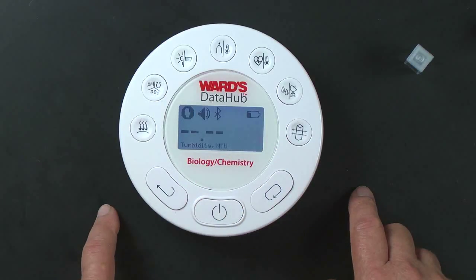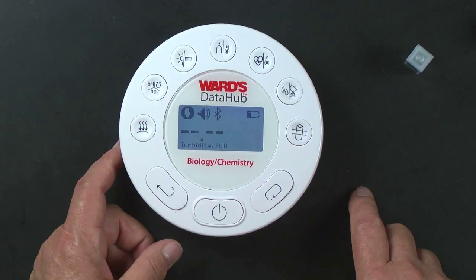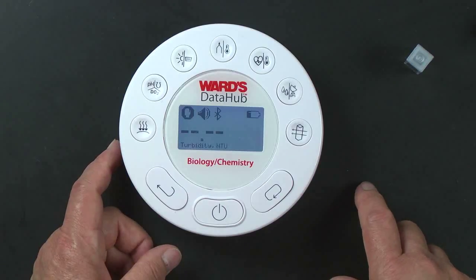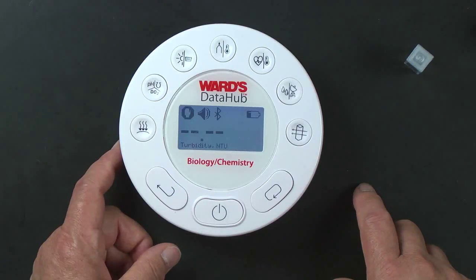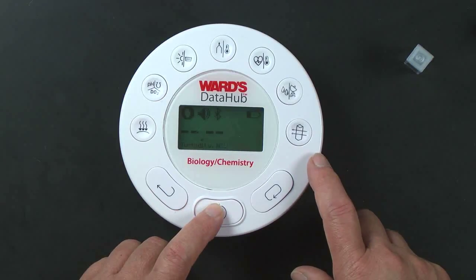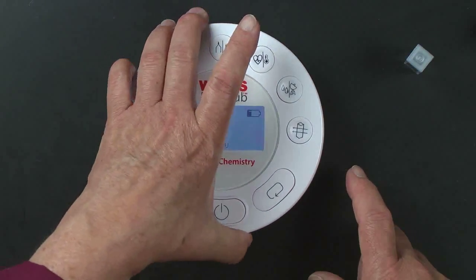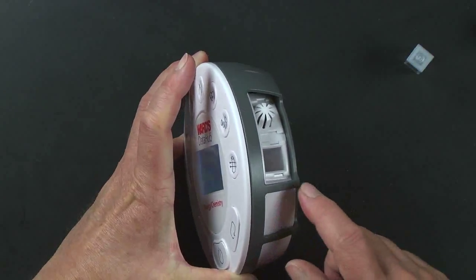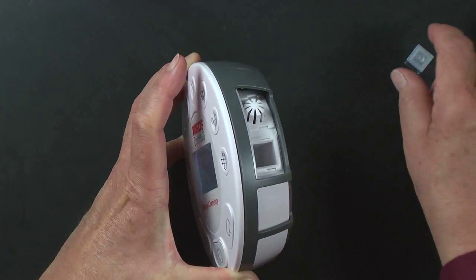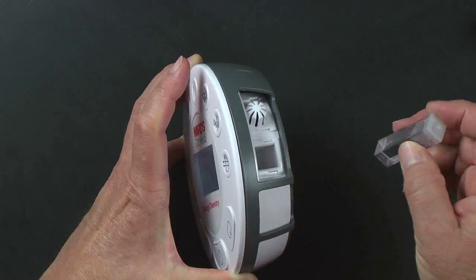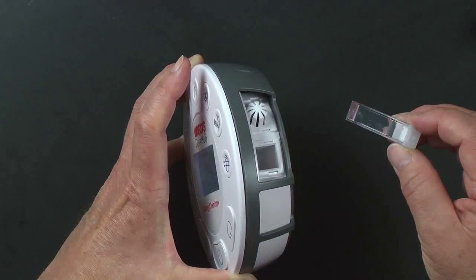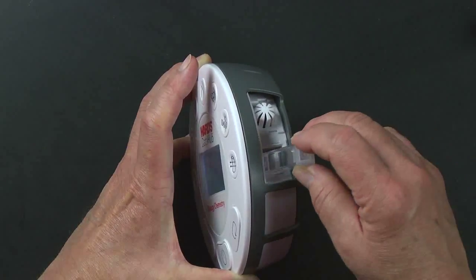and it also tests 3 different wavelengths of color. So it doesn't say, you can't set it as you normally see to 680 or 740 or something on a spectrophotometer, but it will give you a difference in readings. What you can do with these is you turn the Datahub again so that now you can see that there's an opening there, and that opening fits these cuvettes perfectly. These cuvettes are made for that.